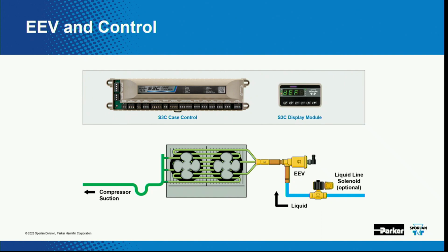With a case controller and a display module - every case controller needs a display module - we can control the superheat on this coil. We can also control the discharge air coming off of that coil, and we'd do that with the solenoid valve. It says optional, but it's really necessary - you really want to have that on there just to be able to shut off refrigerant flow.